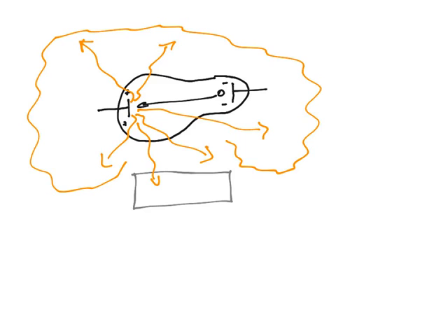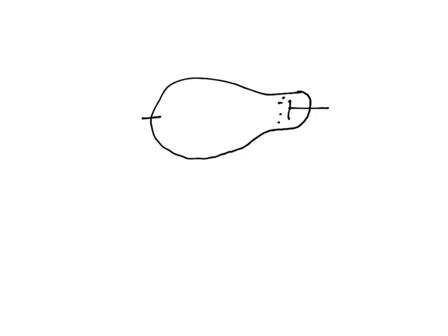And so it had to be figured out how to redesign this and allow you to more able predict, or at least control, where these X-rays are going to go. So the next evolution wound up being a pretty interesting design. They kept, of course, the cathode the way it was, and they, of course, left the anode straight across because that's a very good way to do it. However, now what they did was they designed the anode to be kind of wedge-shaped.